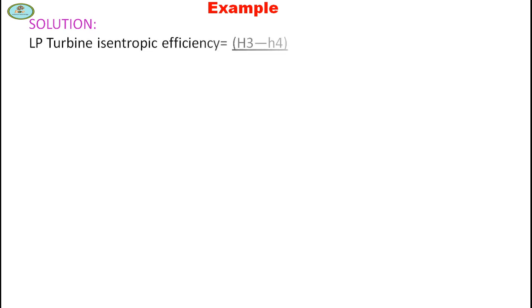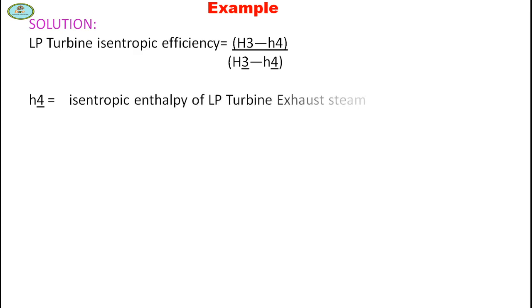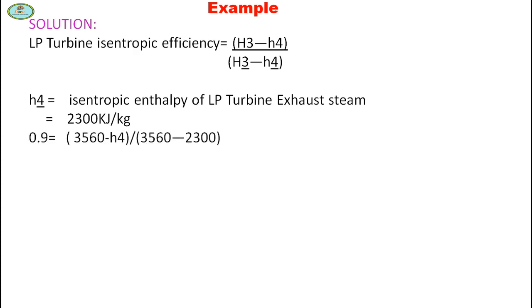LP turbine isentropic efficiency is (H3 − H4) divided by (H3 − H4_isentropic), where H4_isentropic is the isentropic enthalpy of LP turbine exhaust steam = 2300 kJ/kg. Solving: 0.9 = (3560 − H4) / (3560 − 2300), giving H4 = 2426 kJ/kg.